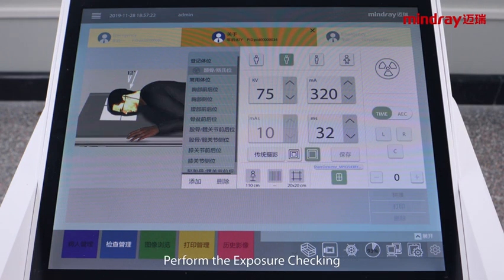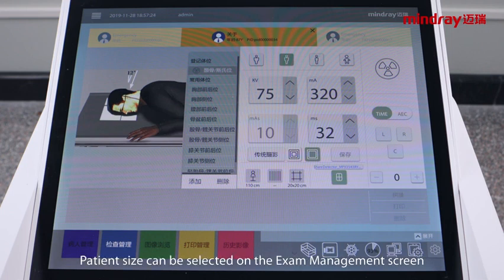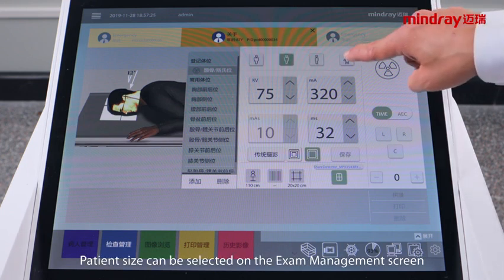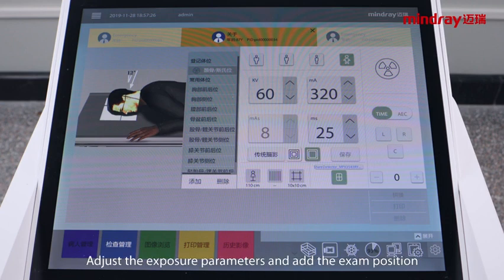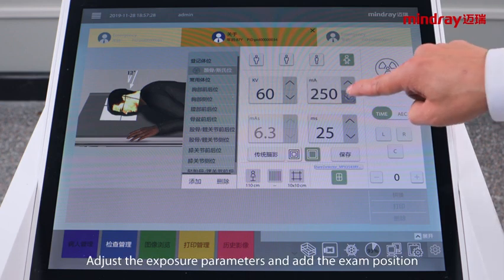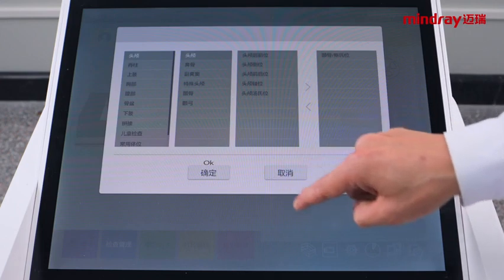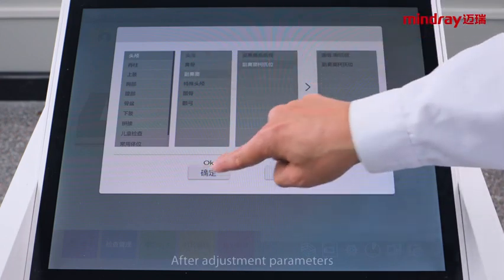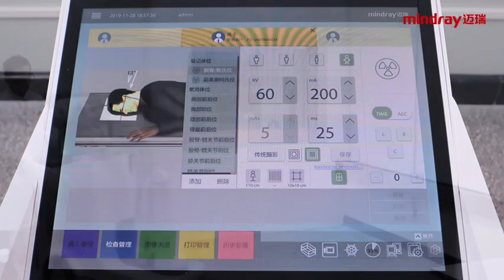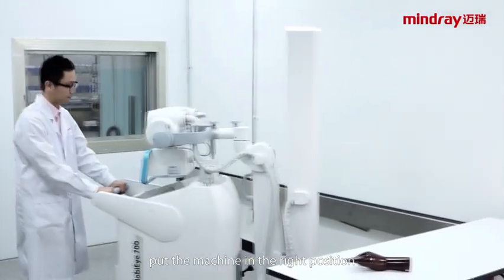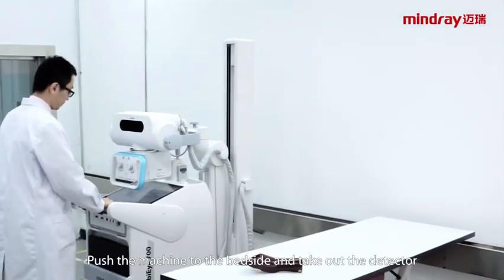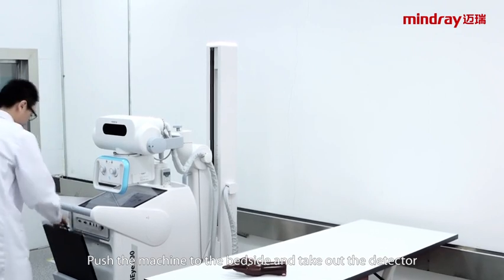Perform the exposure checking. Patient size can be selected on the exam management screen. Adjust the exposure parameters and add the exam position. After adjusting the parameters, put the machine in the right position. Put the machine to the bedside and take out the detector.